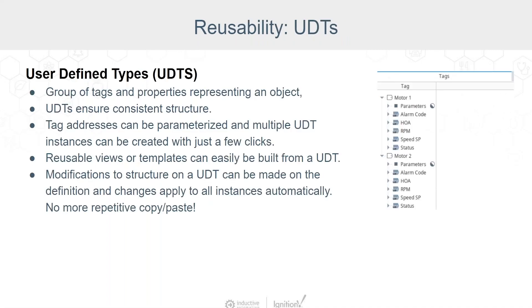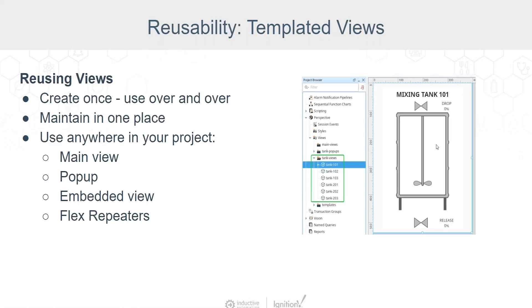Now let's talk about UDTs, or User Defined Types. A UDT is a group of tags and properties representing some object, like a tank or motor. This gives you a consistent structure — every instance will have the same alarms, properties, and folders. Tag addresses can be parameterized, and you can have multiple UDT instances created in just a few clicks. Modifications made on the definition automatically apply to all instances. If you find yourself building a folder of tags and then copying it to create another instance, it's time to build a UDT.